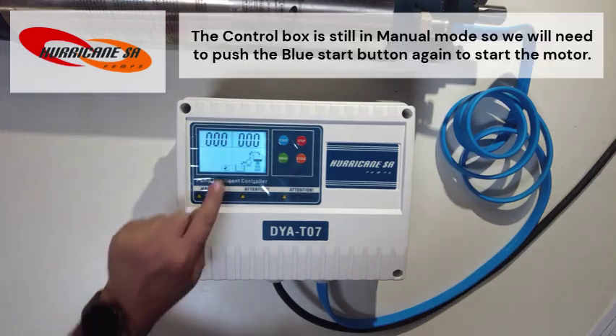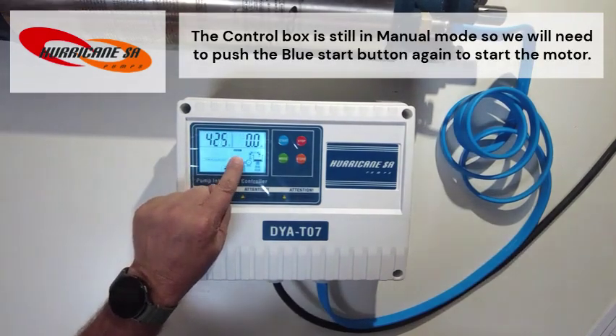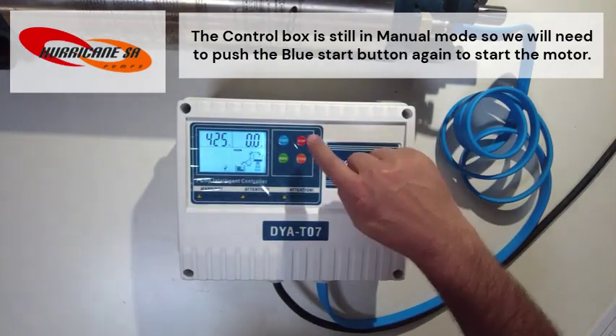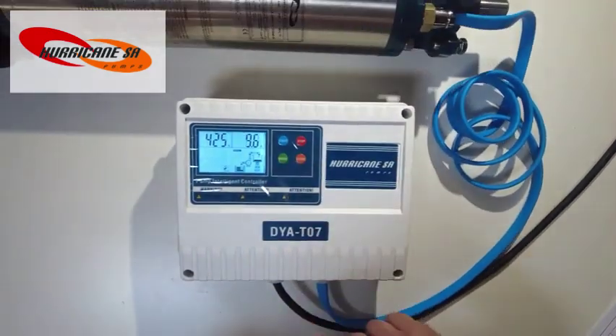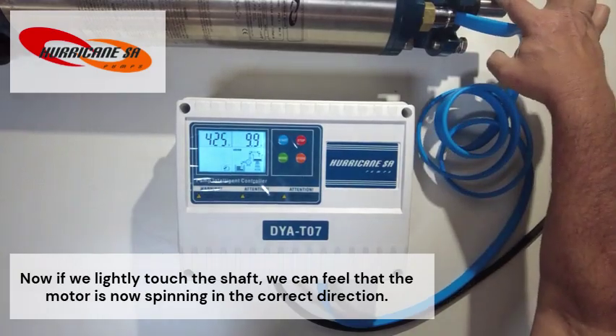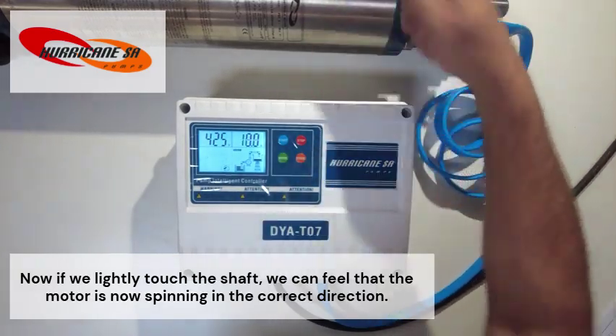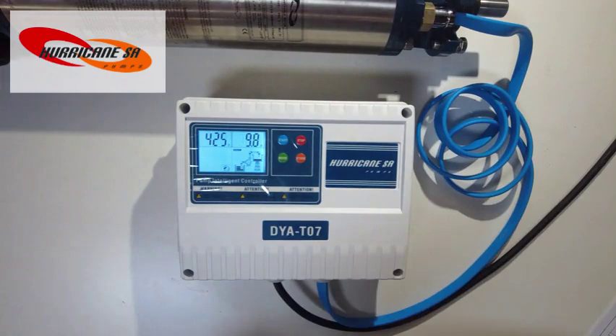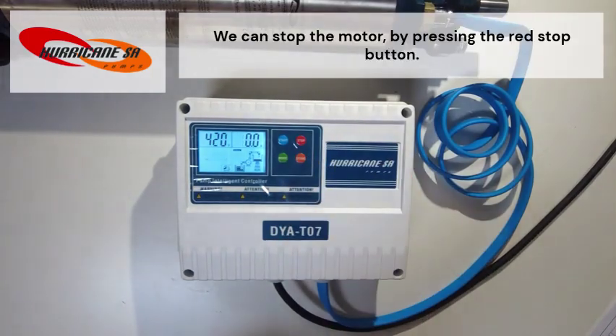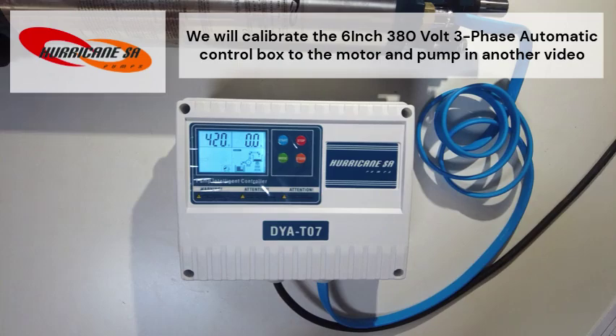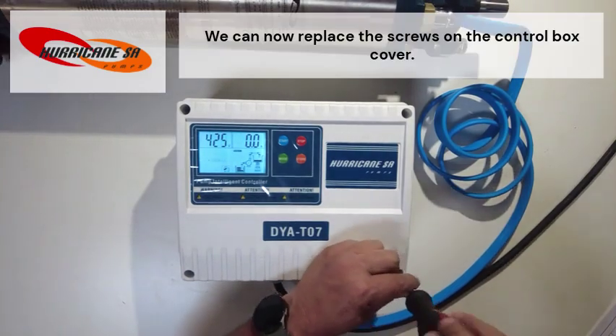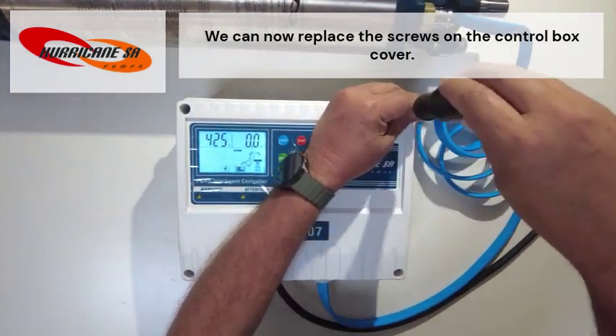The control box is still in manual mode, so we will need to push the blue start button again to start the motor. Now, if we lightly touch the shaft, we can feel that the motor is now spinning in the correct direction. We can stop the motor by pressing the red stop button. We will calibrate the 6-inch 380-volt 3-phase automatic control box to the motor and pump in another video. We can now replace the screws on the control box cover.